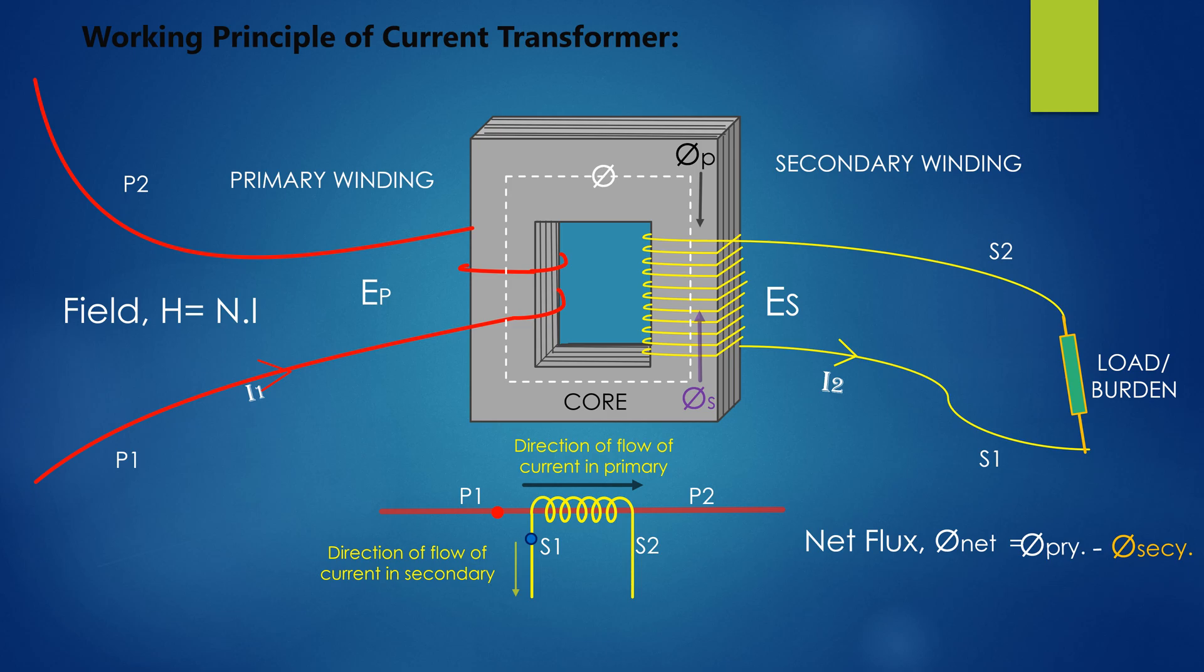The flux in the core remains within the rated current rating of the core when the CT is connected to the specified burden. Then, if the CT is kept open-circuited, no current will flow in the secondary, that is I2, the secondary current is equal to zero. And consequently, no secondary flux, the opposing flux, will be set up in the core, that is phi s is equal to zero. Therefore, net flux phi net is equal to primary flux phi primary.